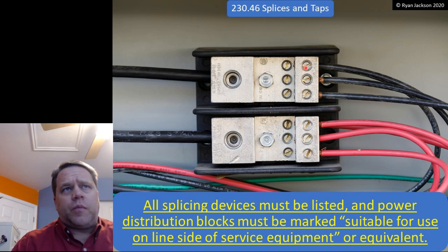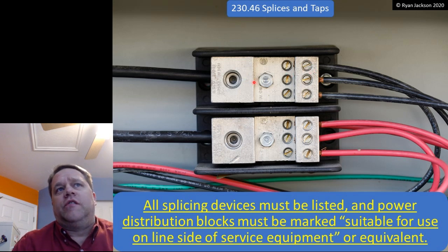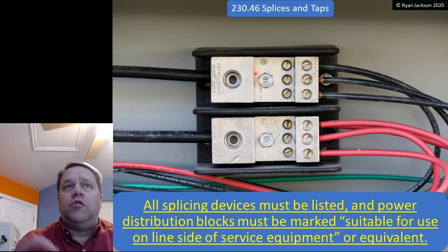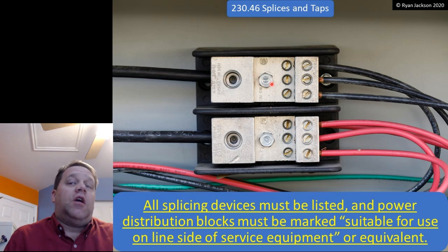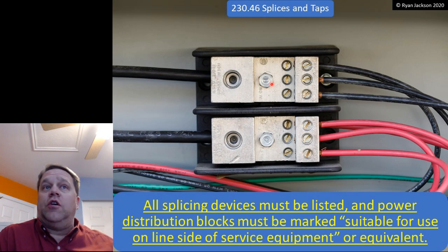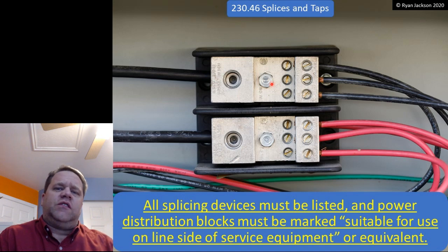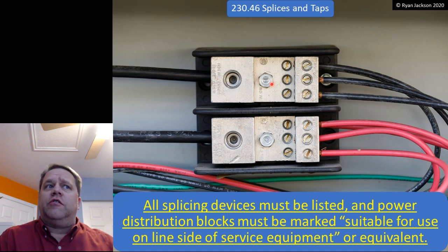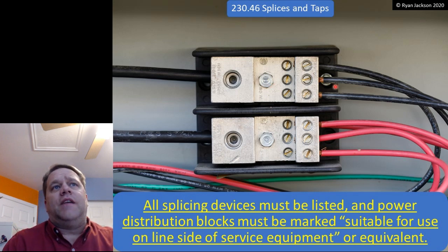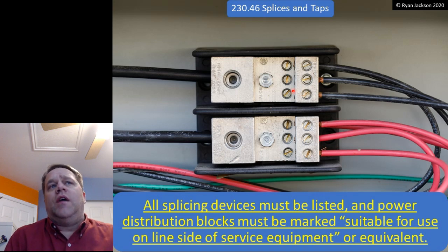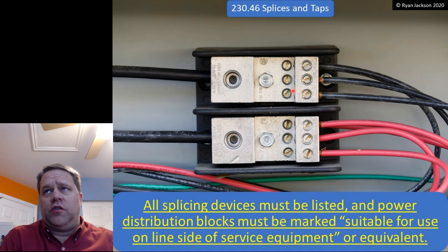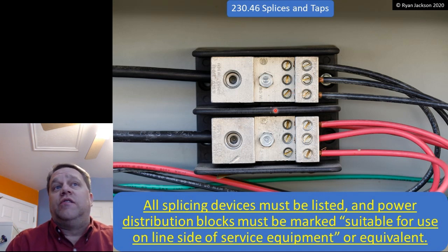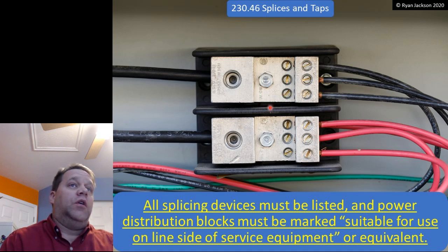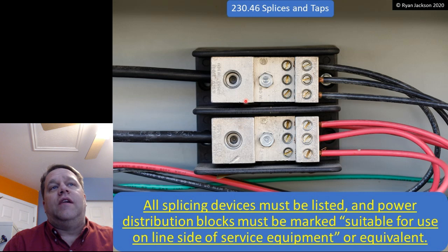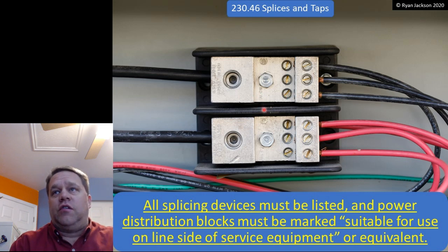The idea here is that if this has a fault and it's on the supply side of the service, this is going to have to carry the short circuit current for as long as is necessary for the utility overcurrent devices to open. When it's downstream of the service disconnect and we have a fault, our breakers or our fuses open quickly, and we don't have massive amounts of current subjected to these parts for very long at all. But on the supply side of the service, we don't regulate how quickly the utility overcurrent devices open. So this might be seeing thousands of amperes for significantly longer than it would downstream of the service disconnect. And that's why it has to be marked suitable for use on the line side of service equipment.